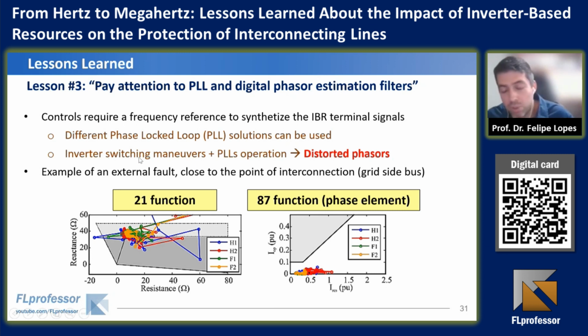And when you consider the inverter switching maneuvers and the PLL operation, distorted phasors can take place. And when I say distorted phasors, I mean the signals may present some distortions with harmonics, interharmonics, but also frequency variations. And when we analyze these distorted signals for different phasor estimation algorithms using half-cycle windows and full-cycle windows, and considering different PLL models, we could see that the distance protection function can be relevantly affected, whereas the phase element of the differential function remained very good. So this is a combination of the distortions in the signals that I presented in the first slides, and also the PLL operation, so we can have some problems like that, besides the rotating characteristics that I have already mentioned.